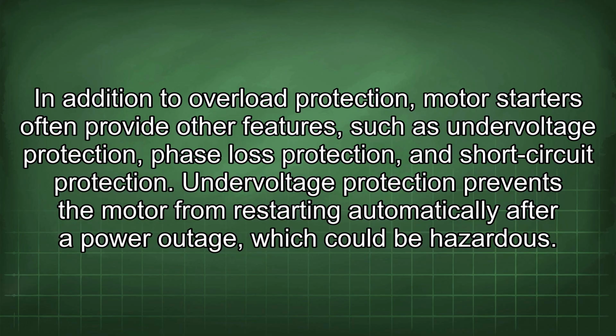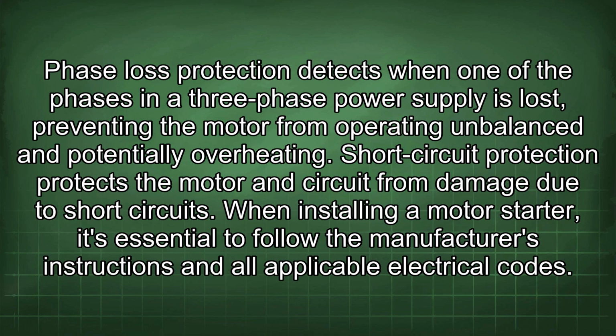In addition to overload protection, motor starters often provide other features, such as undervoltage protection, phase loss protection, and short-circuit protection. Undervoltage protection prevents the motor from restarting automatically after a power outage, which could be hazardous. Phase loss protection detects when one of the phases in a 3-phase power supply is lost, preventing the motor from operating unbalanced and potentially overheating. Short-circuit protection protects the motor and circuit from damage due to short circuits. When installing a motor starter, it's essential to follow the manufacturer's instructions and all applicable electrical codes.